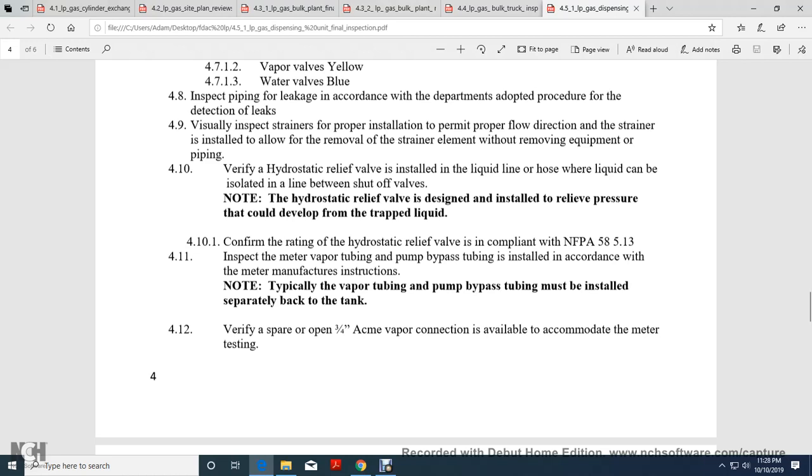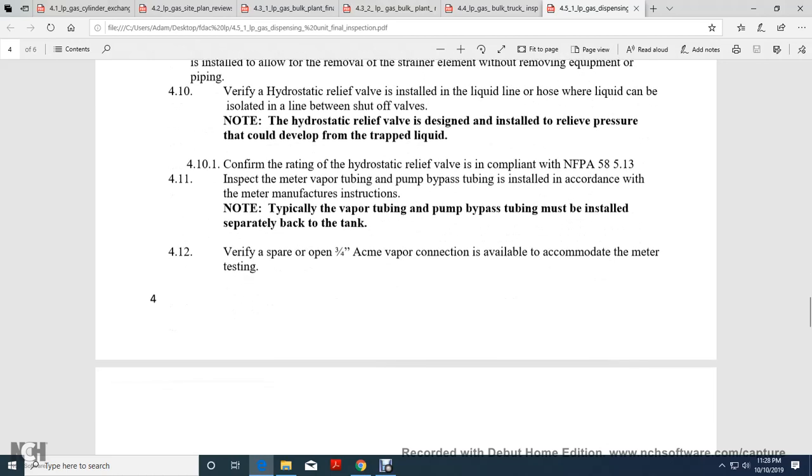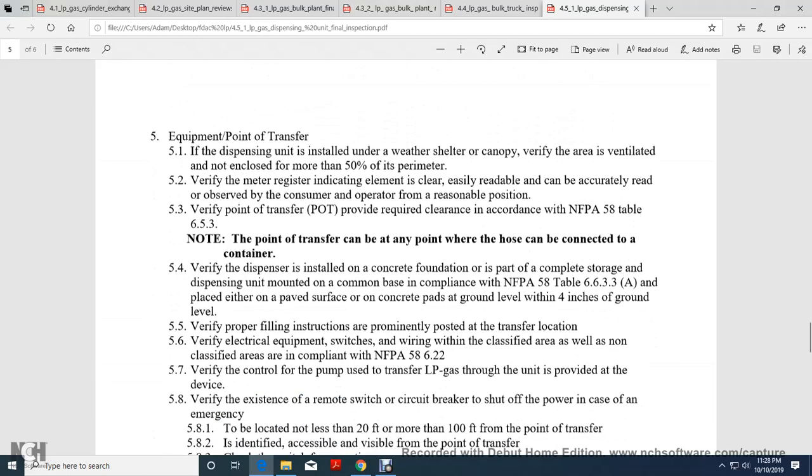Verify a spare or open three-quarter inch Acme vapor connection is available to accommodate meter testing. Equipment Point of Transfer: The dispensing unit is installed under a weather shelter or canopy. Verify the area is ventilated and not enclosed for more than 50% of the perimeter. Verify the meter register and the recommended indication element are clearly, easily, and readily accurately read and accessible to the consumer from a reasonable position.